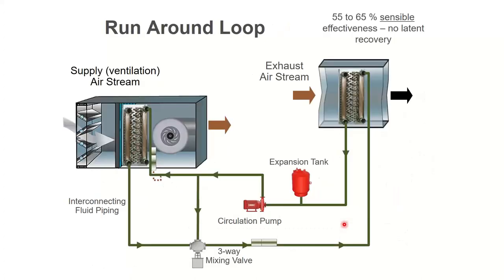I mentioned runaround systems. These are only sensible. You can't do any latents, so you're not going to use these for code compliance, but you may use them in a manufacturing facility or something like that. Basically, you throw an extra hydronic coil on your ventilation air coming in. You throw an extra hydronic coil on your exhaust air going out, and you pump water between the two. So if it's hot air leaving, you pump the water, you get the warm water back, and use it to preheat your outside air. Or if it's the opposite season, opposite scenario, right?